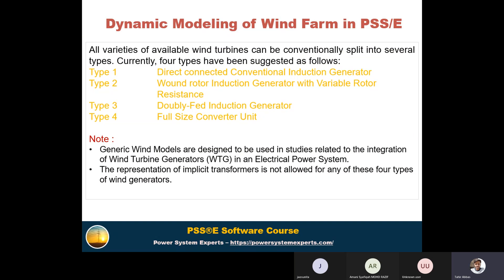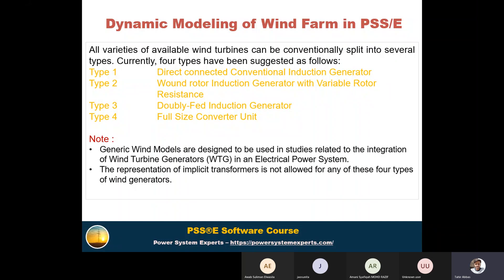In the dynamic modeling of wind farms, there are four types of wind turbines. Type 1 is the direct-connected conventional induction generator. Type 2 is the wound-rotor induction generator with variable rotor resistance. Type 3 is the doubly-fed induction generator (DFIG). Type 4 is the full-size converter unit. These generic wind models are designed for studies related to integration of wind turbines in electrical power systems. Using these generic models, we can also define user-defined models.